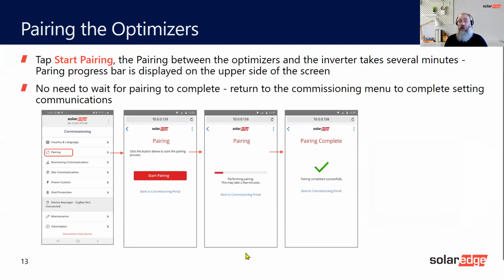Pairing, there's 3 different ways to pair. One we've already talked about, which is holding the switch for more than 5 seconds in the P position. The second one is using setup and pairing. And the third one is via the monitoring. You go to your monitoring site, you can right click on the inverter, and then it says to perform a task or an operation. You click on that and you have 2. One is AC reset, which just basically turns the inverter off. And the other one is to pair. So there's 3 ways you can pair. So if the weather's rather poor, dark, or it's quite late when you finish the job and you haven't paired it, very simple. Next morning, about midday, you can just go to the site and you can pair it remotely.